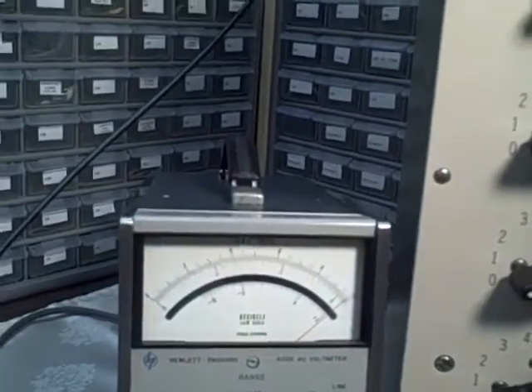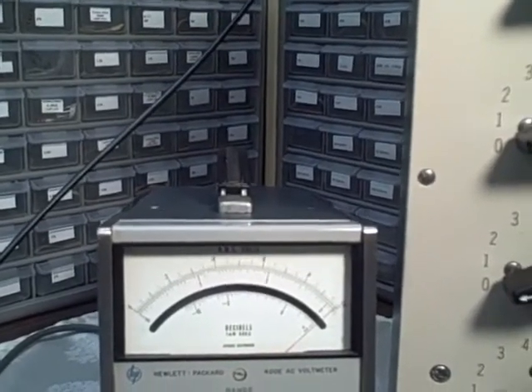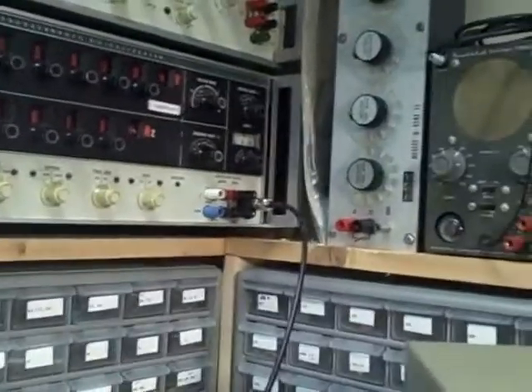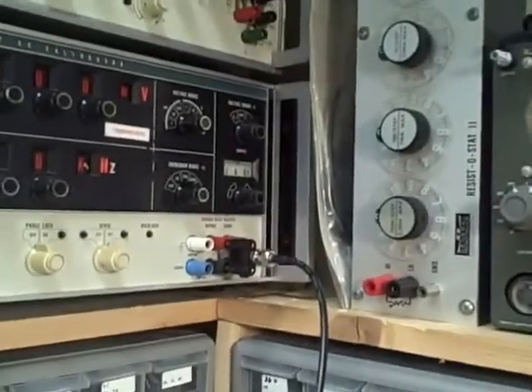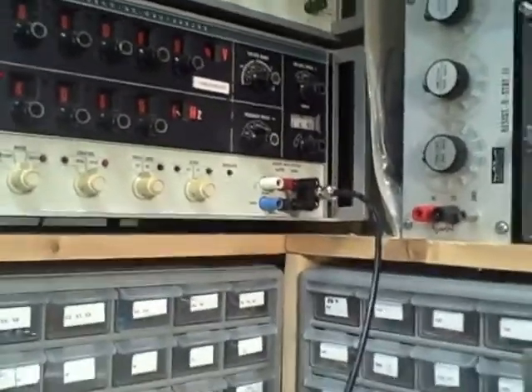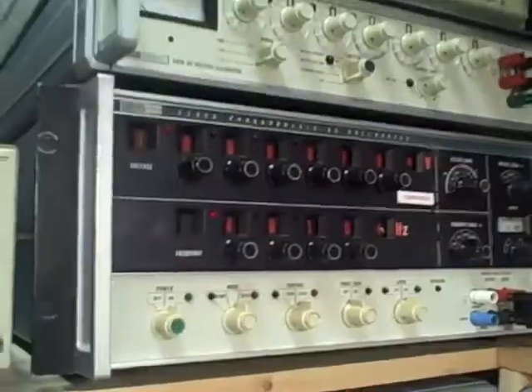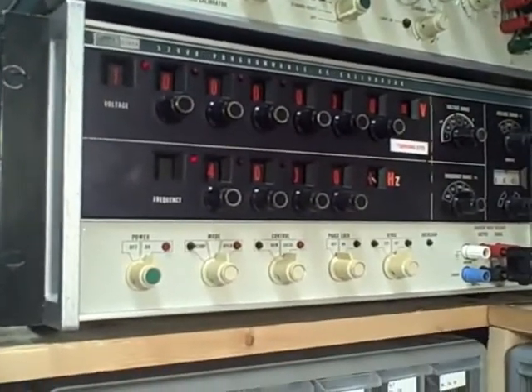Okay, in order to eliminate some of the noise that I was picking up from the surrounding electric wires at the smallest setting of 1 millivolt full scale, I've now connected with a coaxial cable directly to my Fluke calibration standard, and that seems to have quieted everything down considerably. Right now I am feeding in a millivolt full scale at 400 Hertz, and we are at full scale. And then we're going to go and step it down.